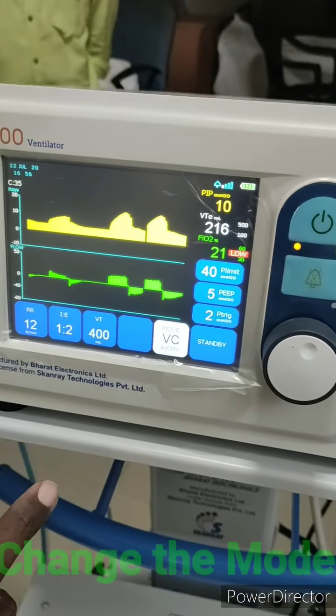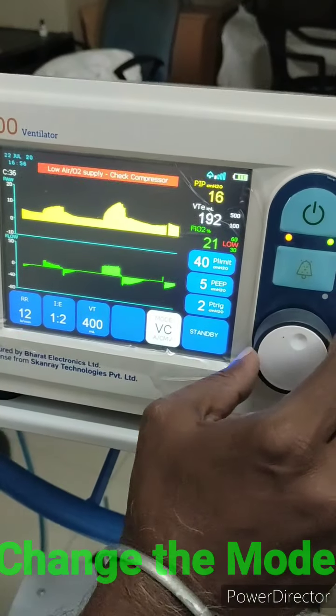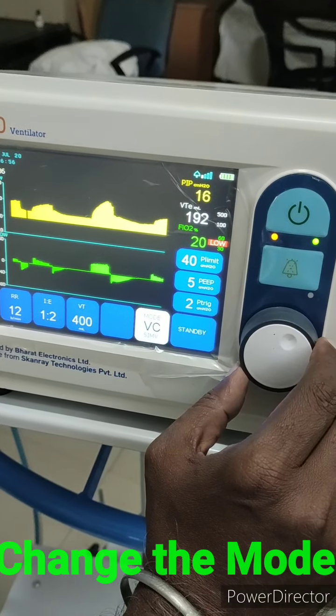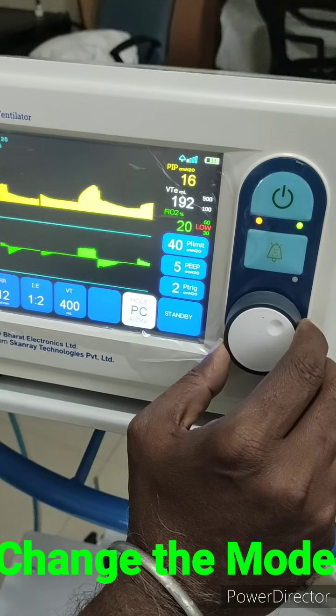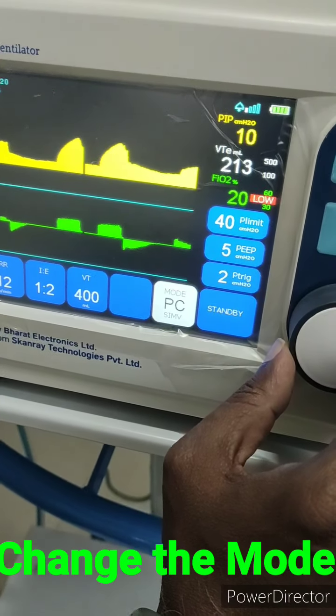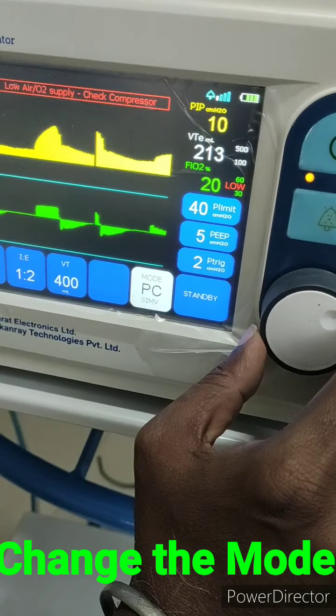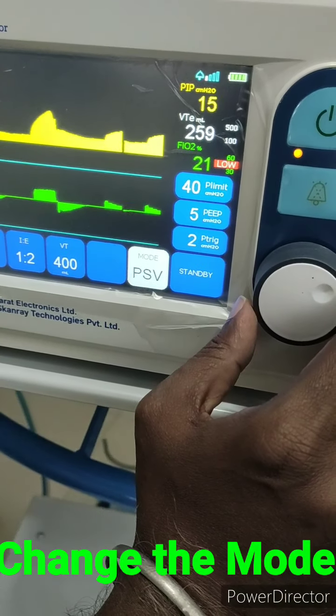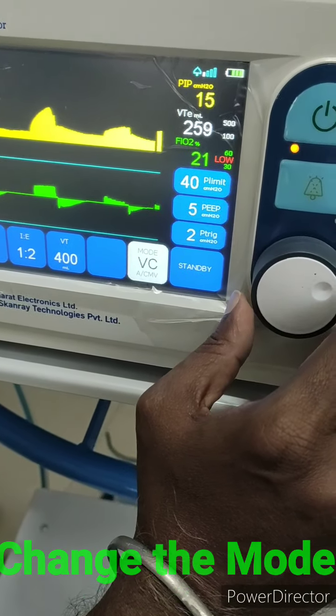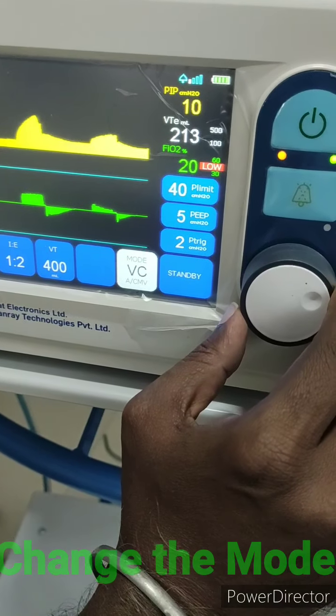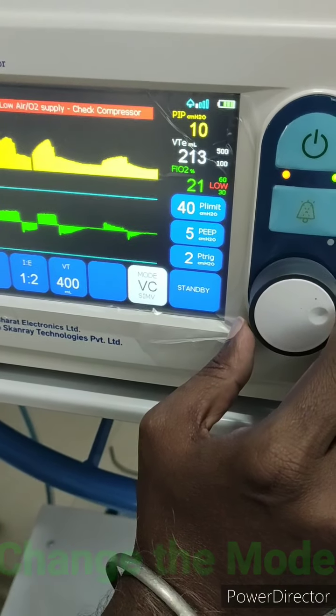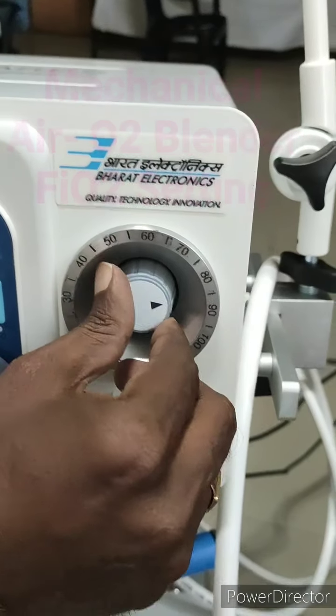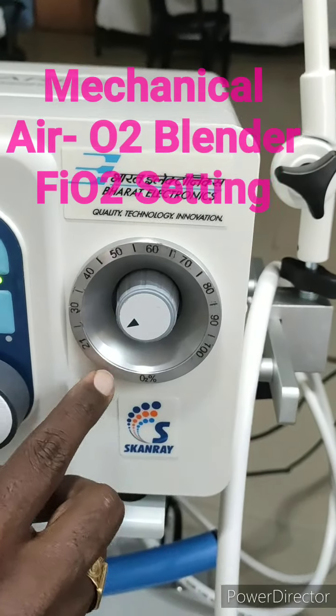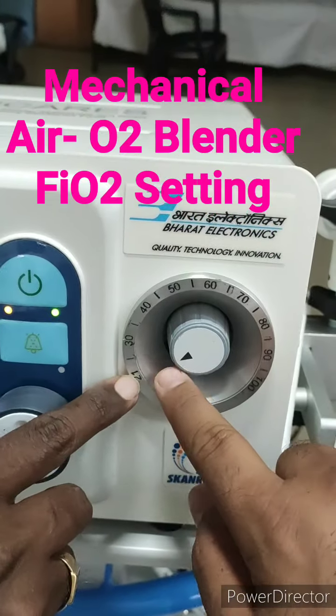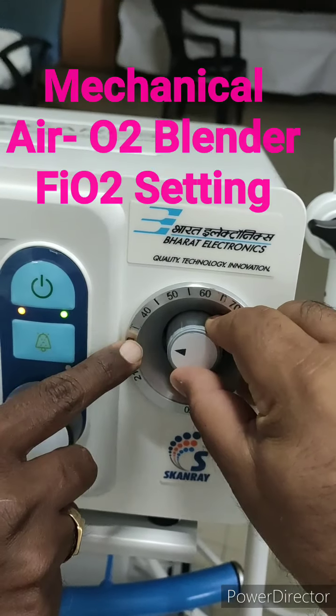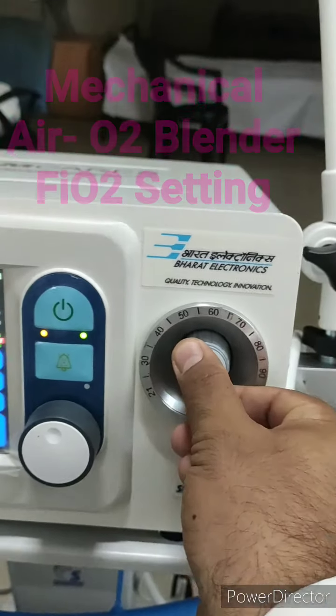This is how we change the mode. This is volume control. And for changing, this is pressure control. Now it has changed to pressure control SIMV, PSV, and volume control AC mode. Okay. This is a mechanical oxygen blender, and this knob will decide how much percent of oxygen you are giving, and this can be adjusted as per the need.